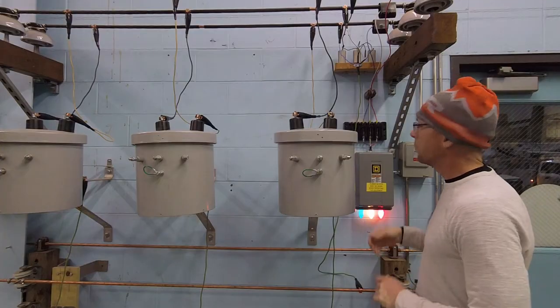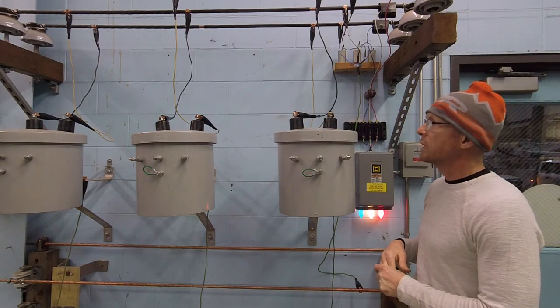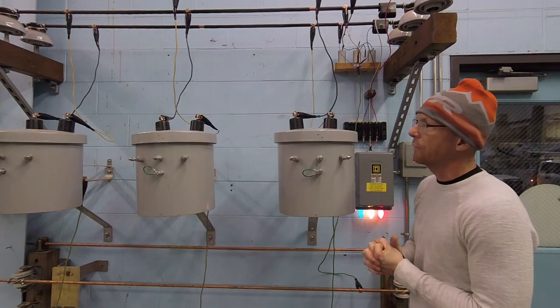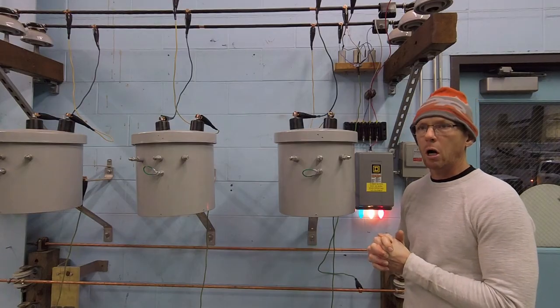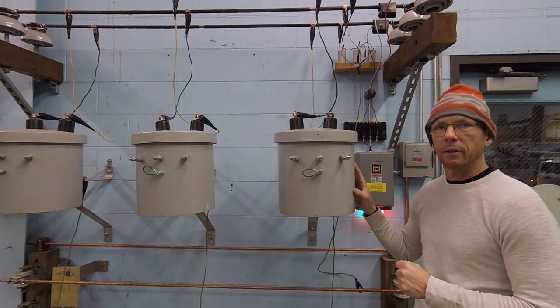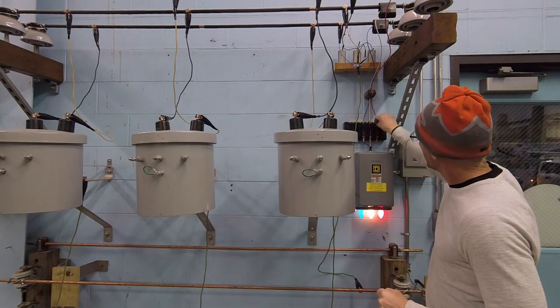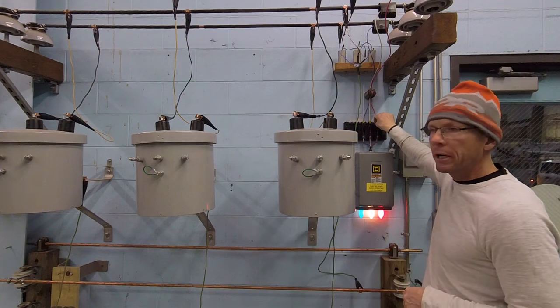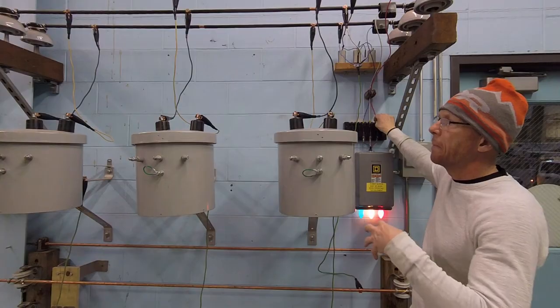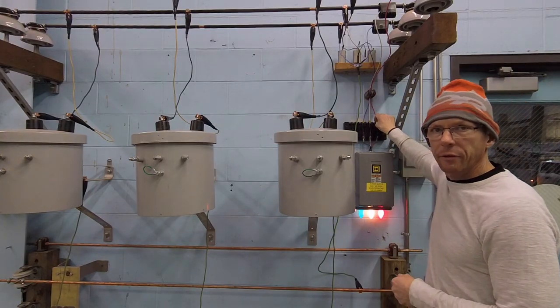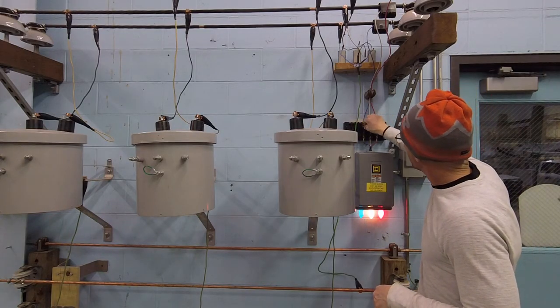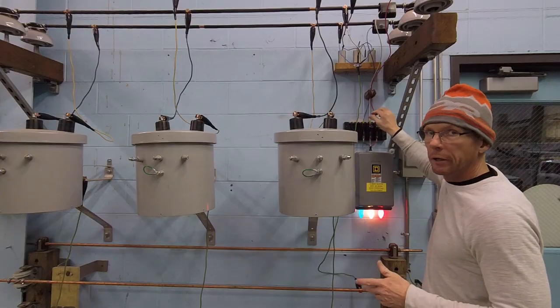So, without further ado, we're going to go ahead and try to stir up the beast and see if we can waken it. This will probably indicate itself immediately by a large hum or an audible noise, a rattling noise, which is going to come out of any of the transformers that are affected by the resonance. I'm going to just begin by opening and closing these switches one at a time. Until such time, all the conditions are right, and this thing will kick off, and you should be able to hear that. And there it is.